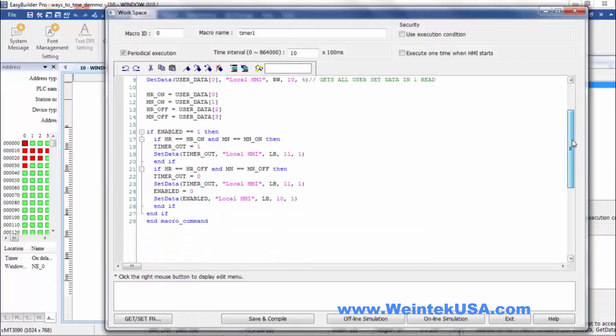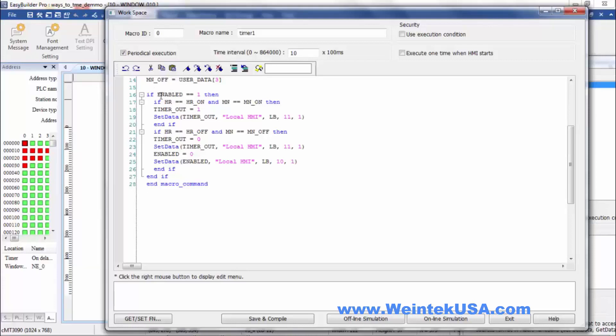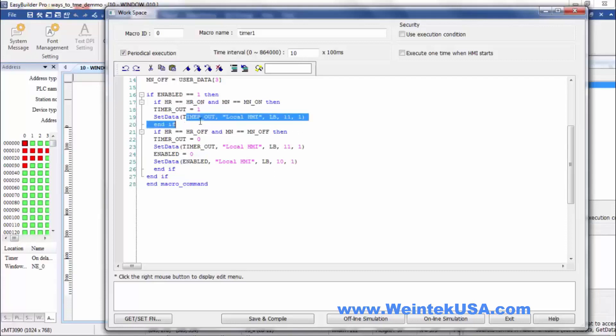And then we've also have our enable bit, LB10, that we're getting the state of that. We're periodically cycling this macro on a 1000 millisecond time cycle. So in the macro we've got all our data loaded into these objects here. So we're doing a compare and if statement, and if enable equals one, then we will go and we'll check the hour. If the hour equals our on hour set point and our minute equals the on minute set point, then we will set this bool value of timer out to one and write that value to LB11 here. That's our output bit.